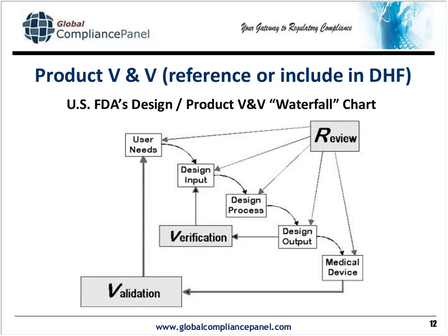The design history file may point to this as a separate document with its own number, probably held in the document control, or it may include copies of that in the design history file. It's a design history file, excuse me, not a device history file. That is up to you as a company to define how you're going to do that. Certainly, if it's a super large document, you'd probably want to have a pointer in the design history file to that document as opposed to including a copy of it in the design history file.